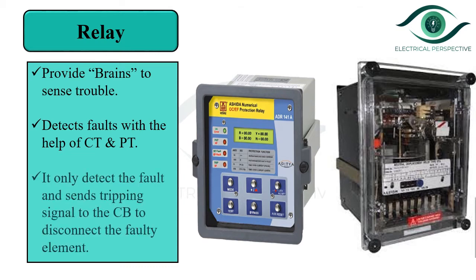Please note that the relay only detects the fault and sends tripping signal to the circuit breaker to disconnect the faulty element. Always remember that relays are low energy devices and they are not able to open or isolate the faulty part. Here figure shows the conventional electromechanical relay and numerical relay, but nowadays electromechanical relays are not in use.